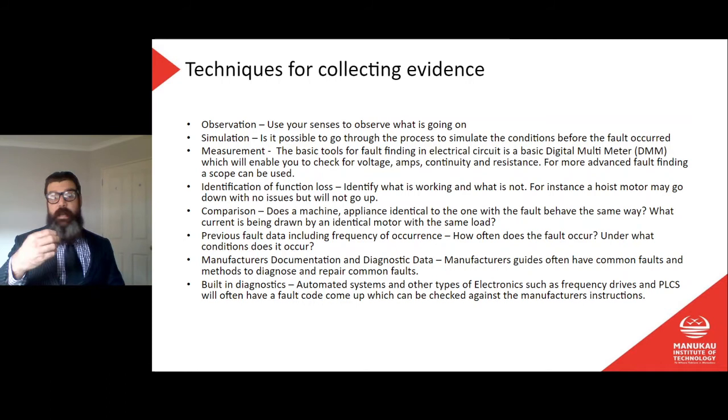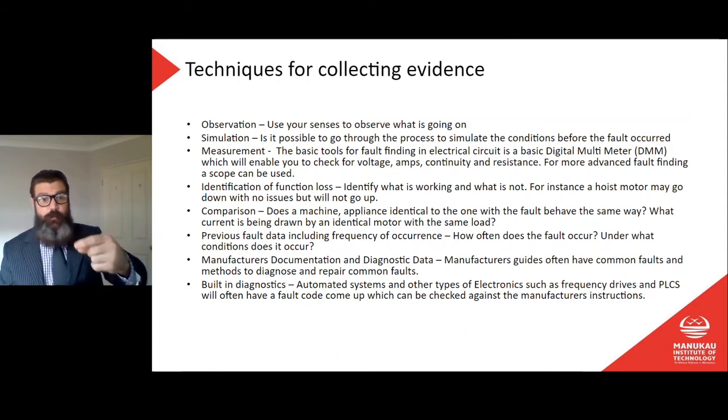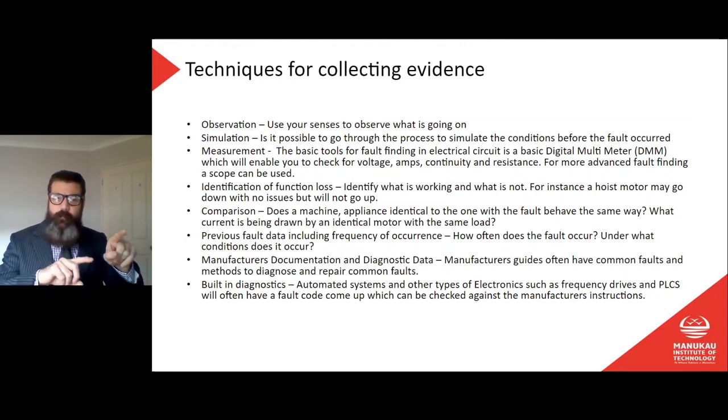Comparison. And so actually, again, as I talked about earlier, the person who's running the thing might not know. They're probably not as skilled as you are. So they won't always know. They'll just go, I don't know, it's not working. Well, you might have to do that yourself and go through and run the thing and figure out, oh, hang on, some of this is working, some of it's not. What are the things that are not working? Because once you've figured that out, that's going to tell you what your fault is.